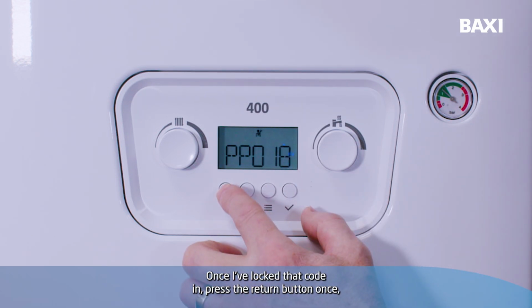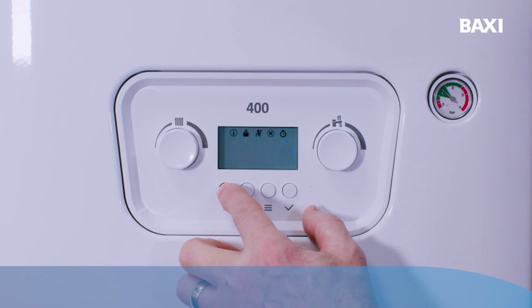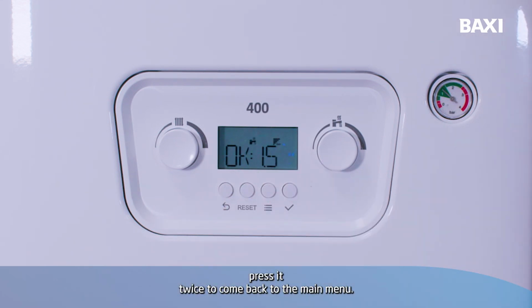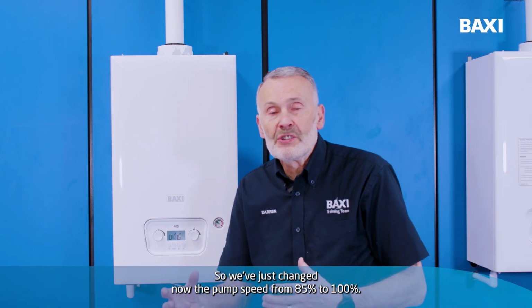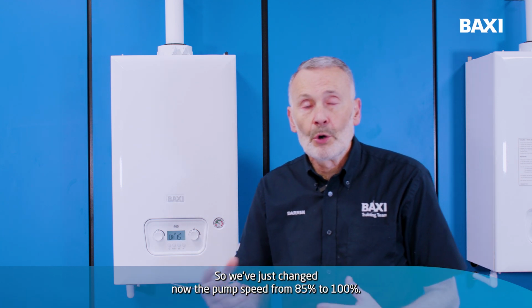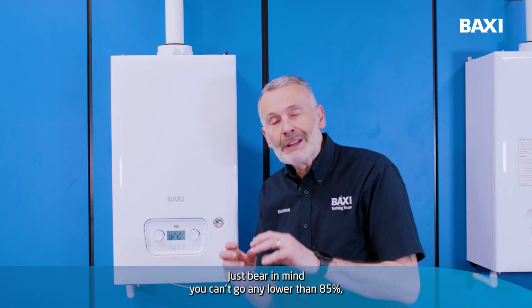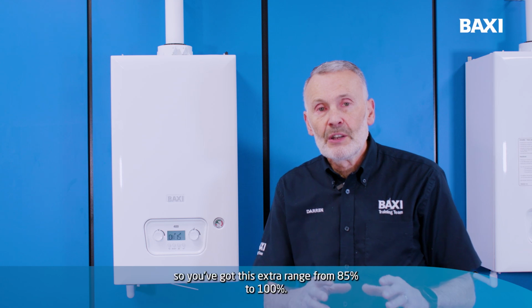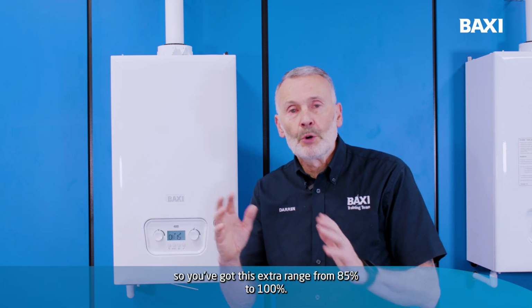Once I've locked that code in, press the return button once, press it twice to come back to the main menu. So we've just changed pump speed from 85% to 100%. Just bear in mind, you can't go any lower than 85%. So you've got this extra range from 85 to 100.